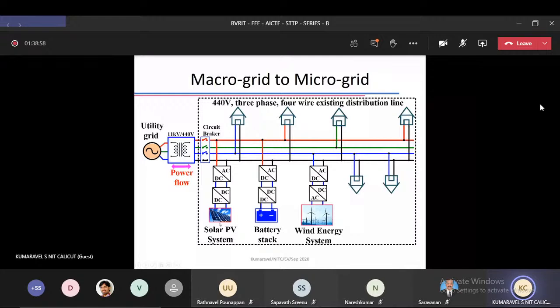When you see the circuit breaker, when it is closed, it will operate in grid connected mode, so that your solar PV, wind, everything will operate in MPPT, that is maximum power point tracking. You all know that. So when it is operating in MPPT, solar PV will inject its maximum capacity.